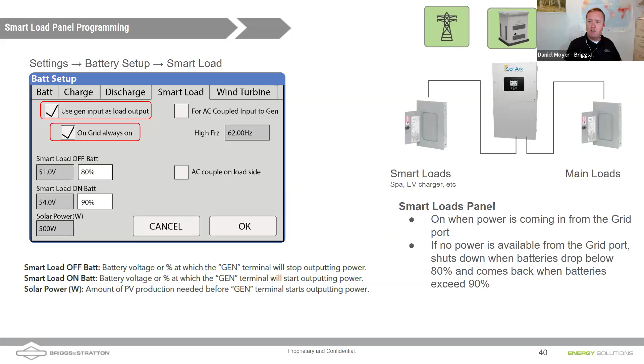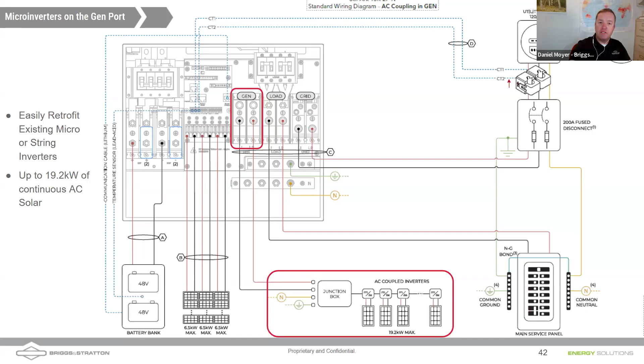AC coupled solar, this is common, right? We come out to a house that already has existing solar, maybe microinverters, maybe a string inverter. We want to bring it in. So instead of that load port or that sub panel on the smart load port, now we're bringing in AC coupled inverters. We're sending power into that gen port.